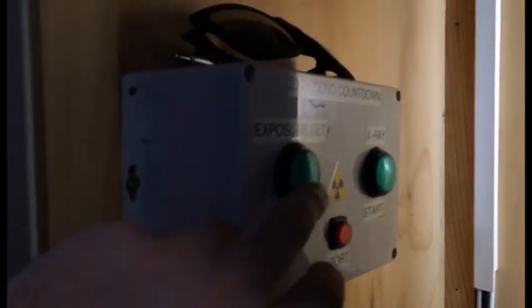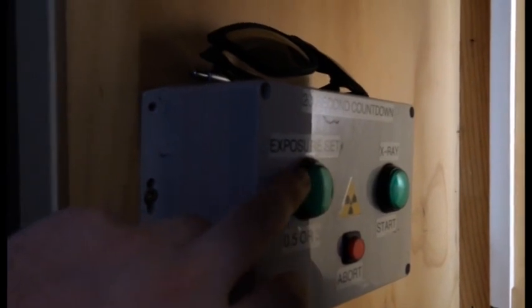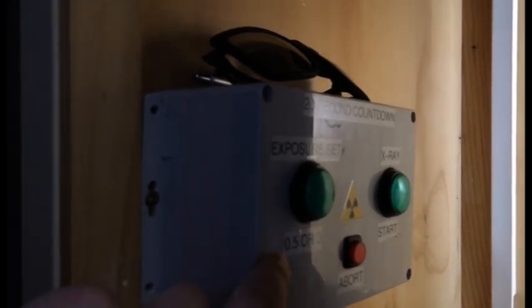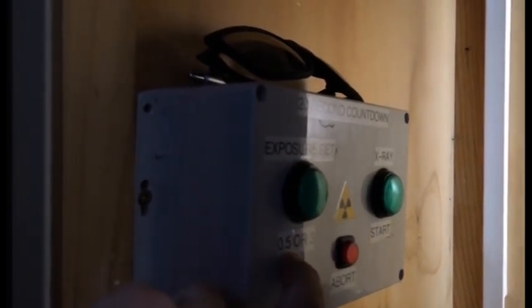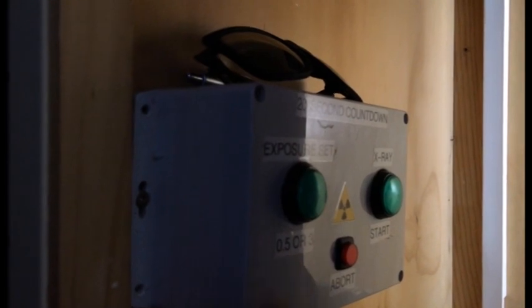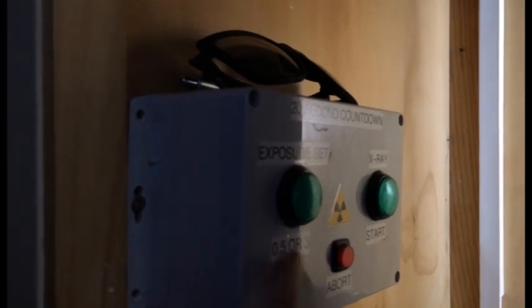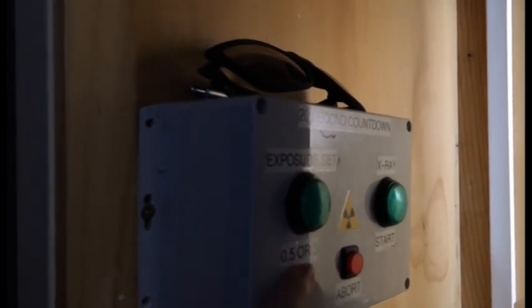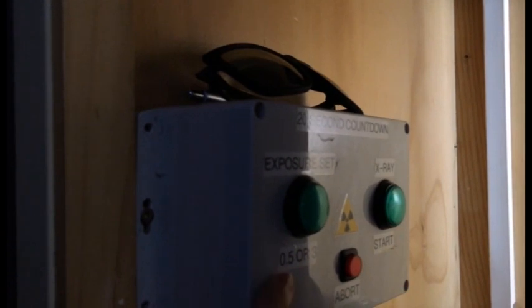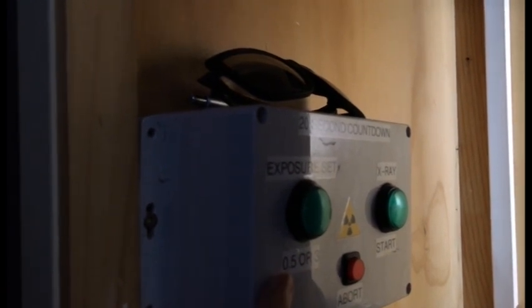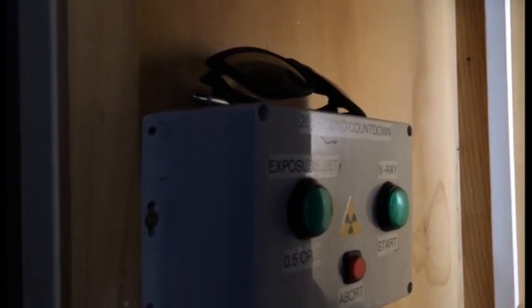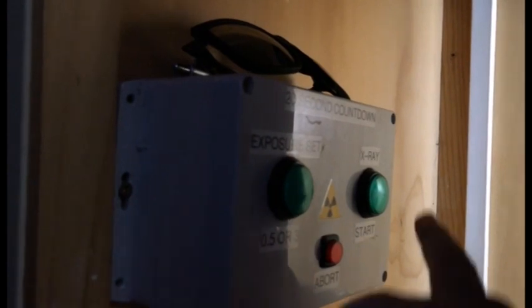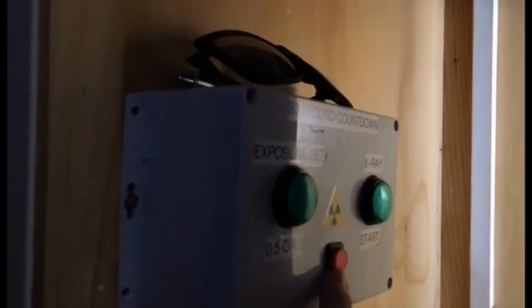And finally, we have the X-ray controller itself. So here you have the exposure set button, so you can choose either 0.5 second exposure or 3 second exposure. I've been sticking to 3 seconds at the moment because I don't have a great camera, but if I had a DSLR, 0.5 would be much safer, because that's not a very long exposure at all. You've got your start button, and you've got your abort button.